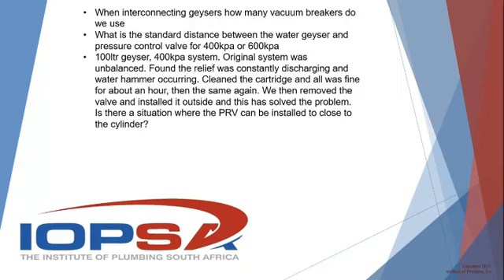So I spoke to the other manufacturer, QuickHot. They had no specifics on it. There's also nothing in the specifications on the valve. I spoke to the factory, and they said they do not have a problem if it is further than 10 meters. But obviously, you must bear cognizance. You can't go and put it 30 or 40 meters away from the geyser. So the only specific I could find was on the Cobra master flow valve, that they specified it must be not further than 10 meters.